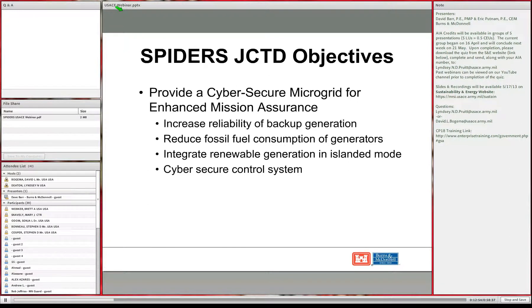Phase one demonstrated operating the microgrid independently and incorporating PV. During testing, the system was configured so that 90% of load came from the PV array while the remaining 10% was supplied by the diesel generator. This created an unusual operating condition for the generator—very lightly loaded and providing all reactive power—but the system was extremely stable and the PV array was completely unfazed. The system operated in this configuration for a sustained period as a successful test.